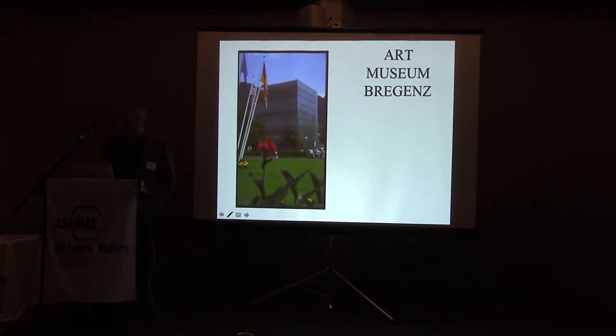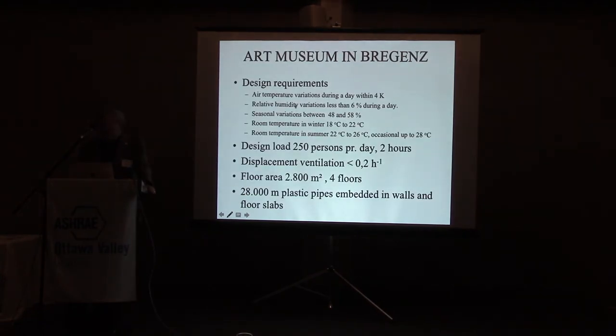Now, when we go to the TABS system, I'll show a couple of examples of that. One of the first ones was an art museum in Austria, by a Swiss architect. It's a three or four story building. It has a kind of double facade. The outer facade is glass, but in between there were concrete walls. And the design requirements, because it was an art museum, were that you could not have too fast air temperature changes during the day. It could vary within 4 degrees, and you want to design the room temperature from 18 to 22 in winter and 22 to 26 in summer.